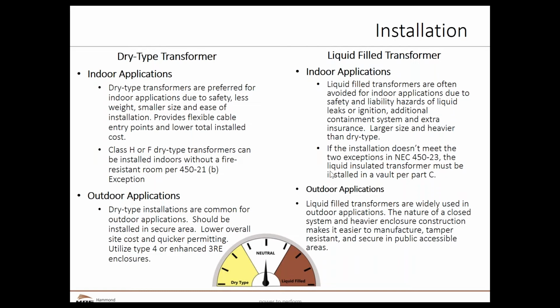Dry type transformers provide flexible cable entry points. So basically, I can come in from the top, bottom, sometimes from the sides, if I'm trying to come into a dry type transformer and either get power out of it or bring power into it. So it's very flexible for things like cabling or conduit.